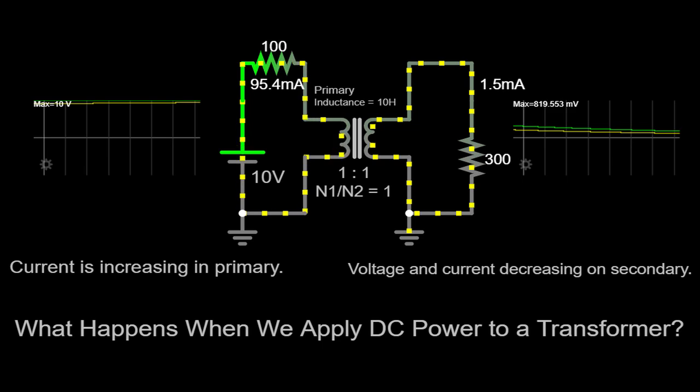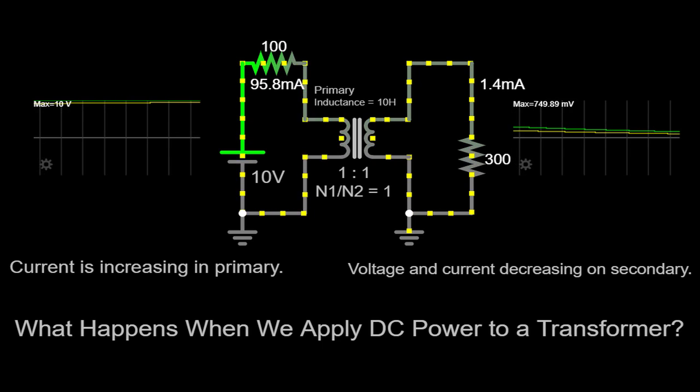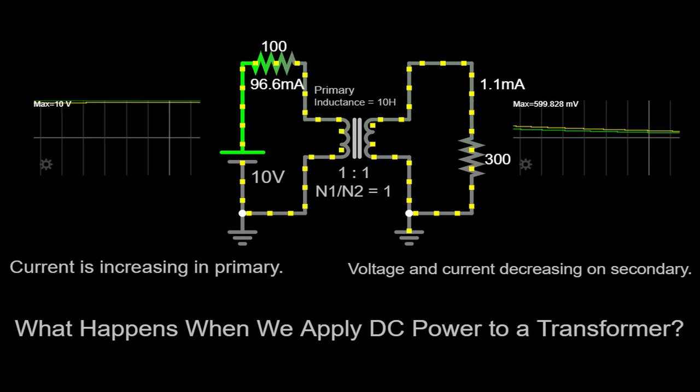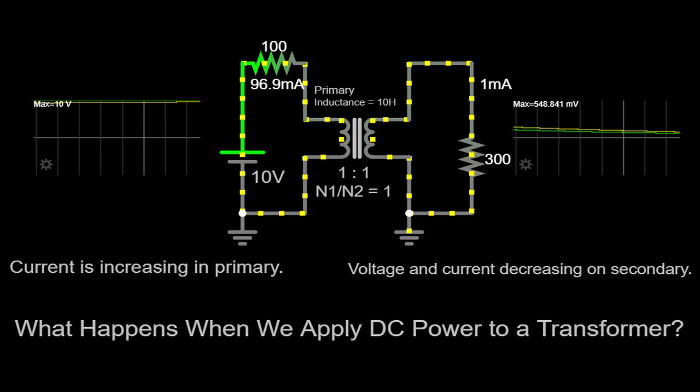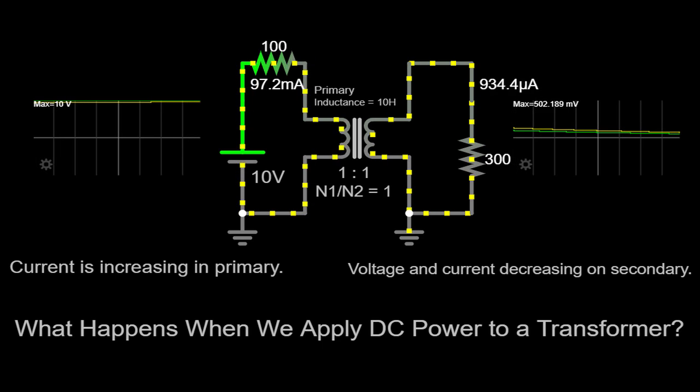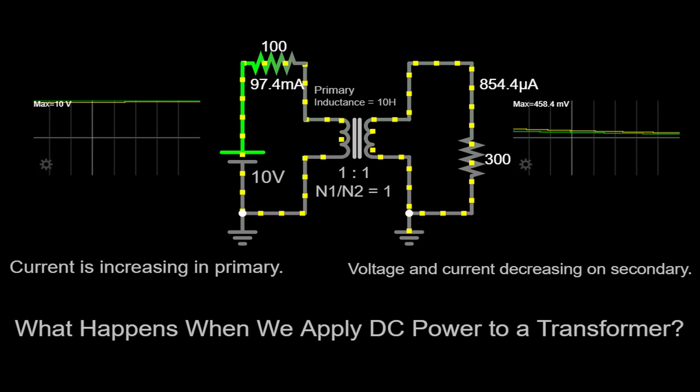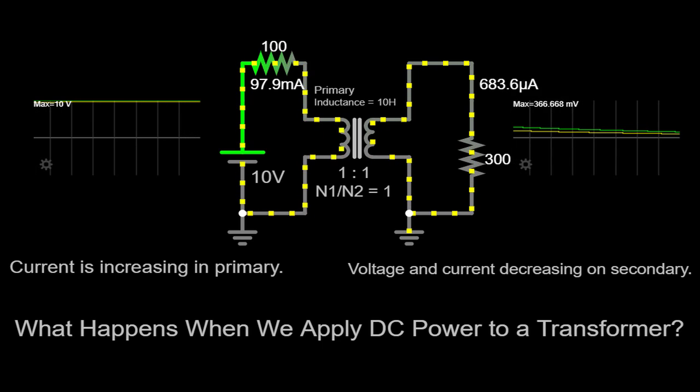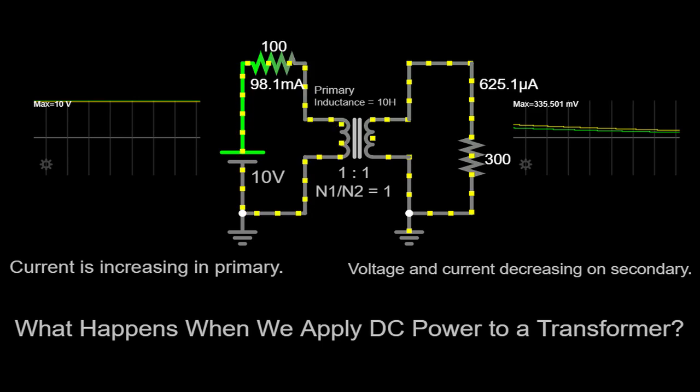Applying DC power to a transformer can have various consequences, depending on the design and specifications of the transformer. One notable consequence is the increased heat generation due to the magnetization current flowing continuously in the primary winding. This increased heat can be detrimental to the overall efficiency and lifespan of the transformer.